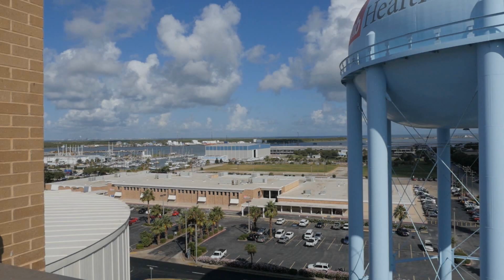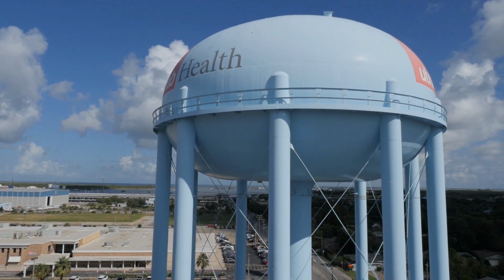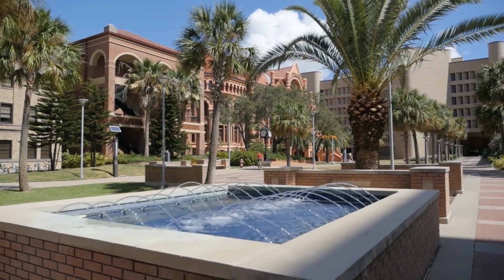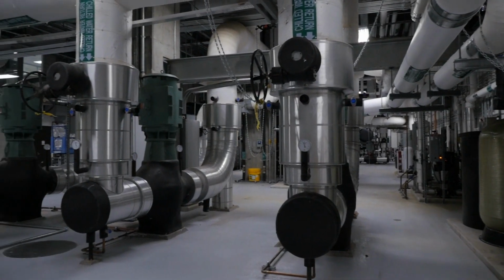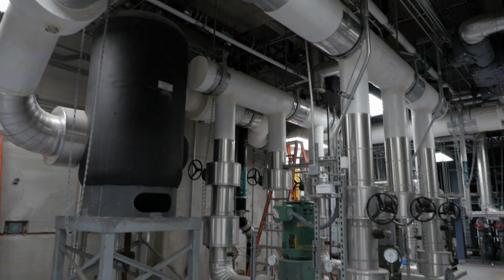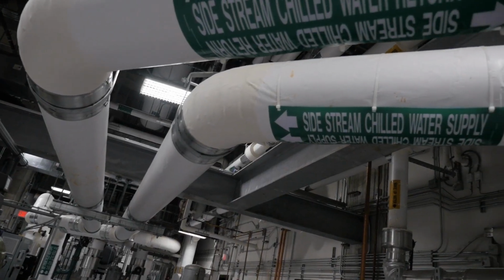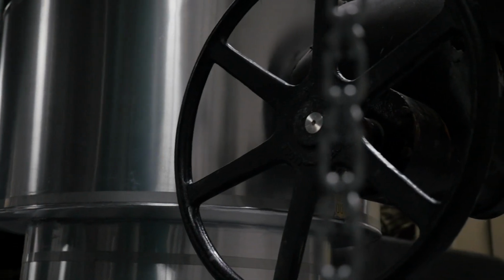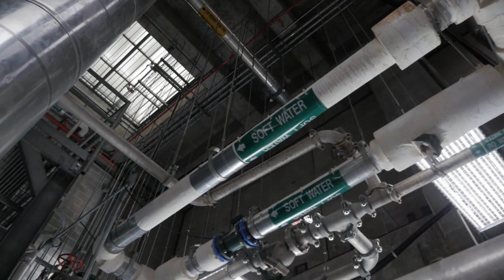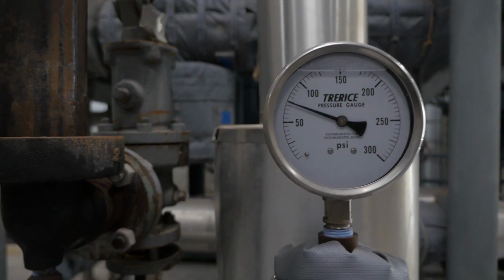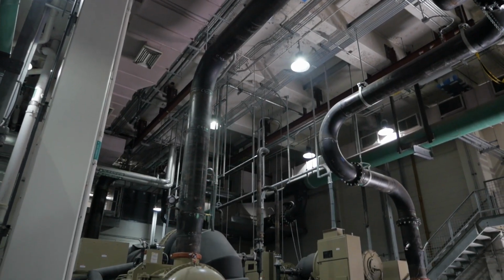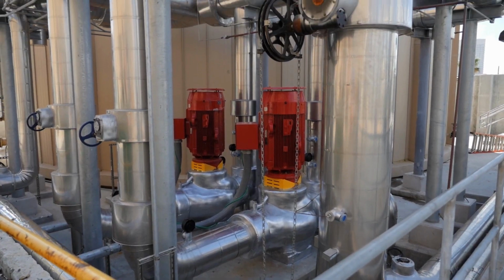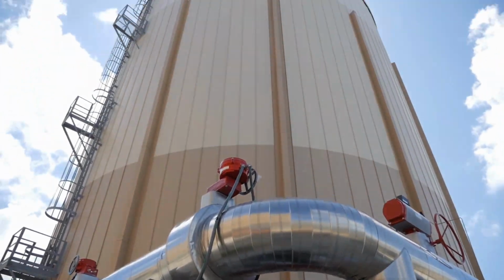Today, the Thomas Mackey Water Plant, which is part of the Gulf Coast Water Authority, had to shut their plant down, shutting off total supply of water to this barrier island. Our plan included a 4 million gallon thermal energy storage tank. What we thought was unique about our application of thermal energy storage is we lined up the system to also be used as an emergency supply of water for our cooling tower. So we have 4 million gallons of processed water available to us that before the event of Ike we did not have.